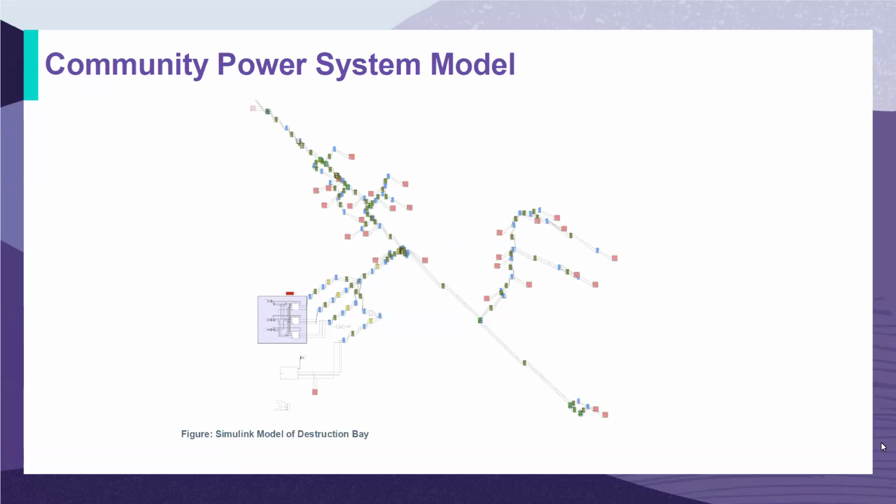So we can not only say, hey, there's a voltage deviation. We don't just say that you have a voltage deviation. We could say you have an over voltage of, say, 1.3 per unit at phase C at this exact pole, to that level of detail.